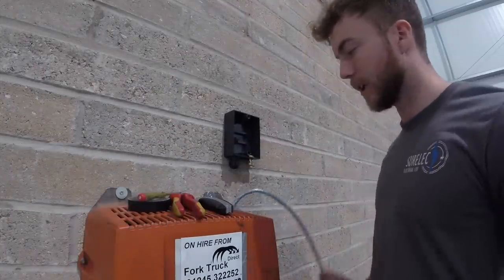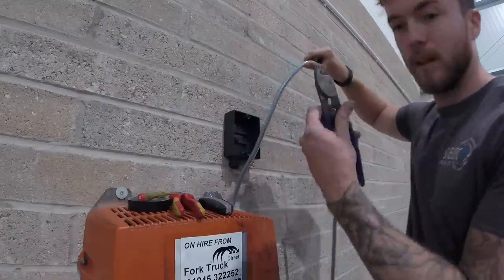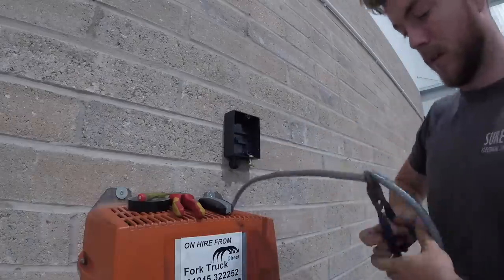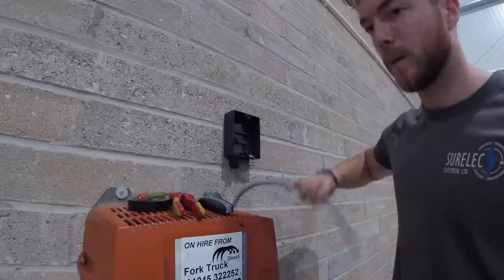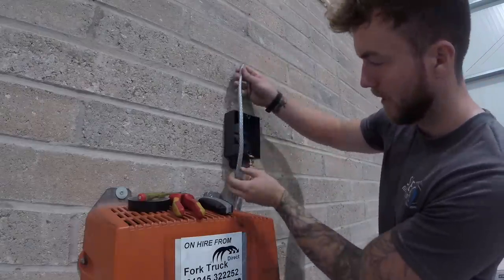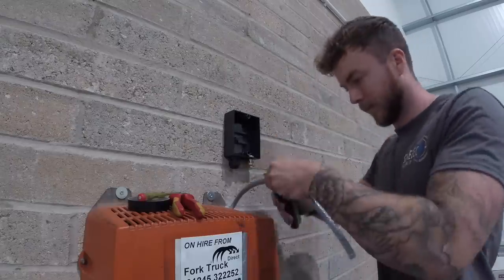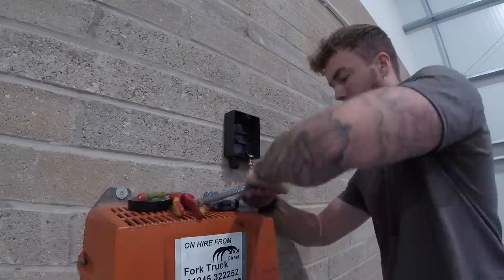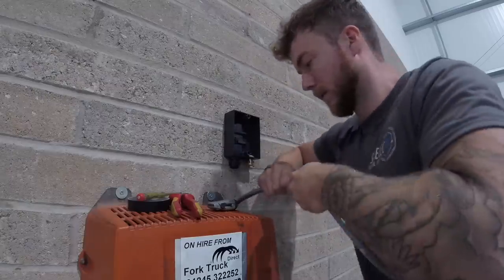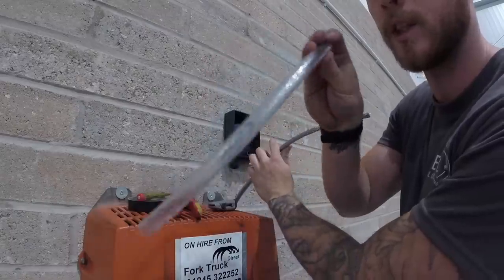I've got the isolator on the wall. First thing I'm going to show you is making off this SWA cable. First, cut it to length — I've just gone a bit past the box. Using a pair of shears, it's fairly easy to cut. Now you want to strip back the outer clear sheath just past where it comes through into the stuffing gland. All you need to do is ring around with a Stanley knife, give it a break either side, and it should eventually just pull straight off. There's the clear outer sheath of the SWA.